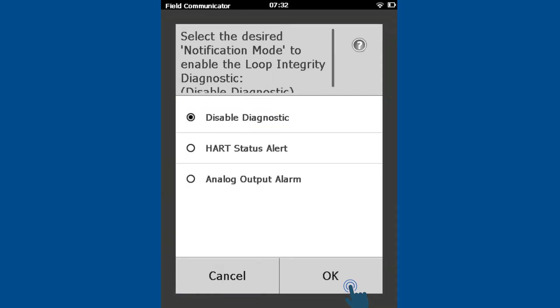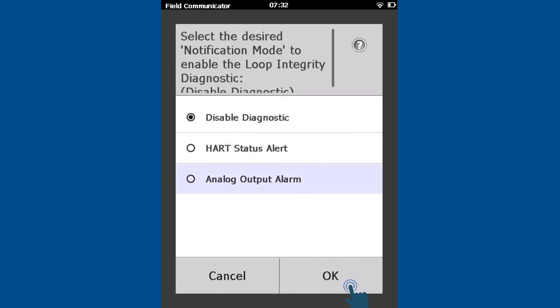Finally, choose your desired notification mode for when deviations are detected. HART Status Alert will generate a HART alert and clear itself when the transmitter identifies that the event has been resolved. Analog output alarm will drive the transmitter to its alarm setting.